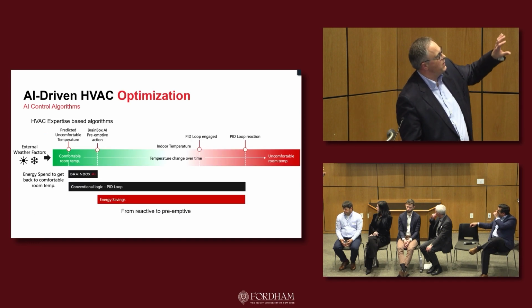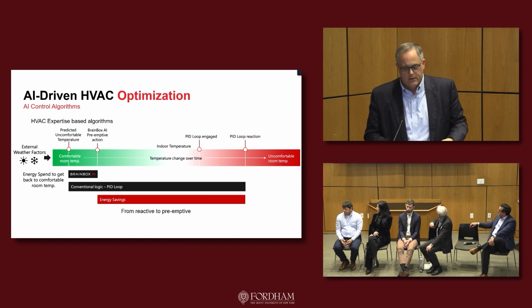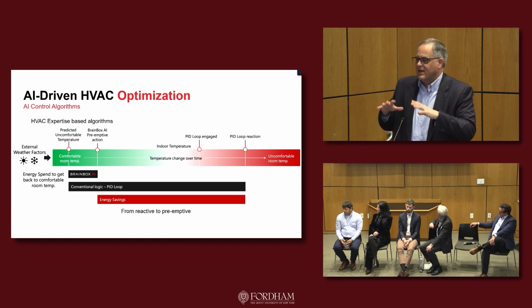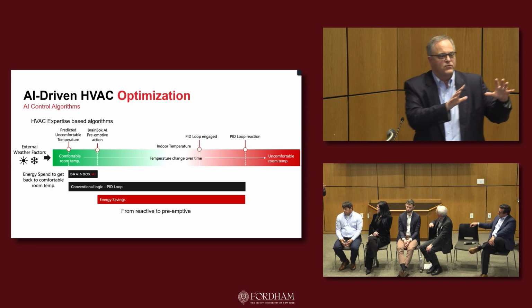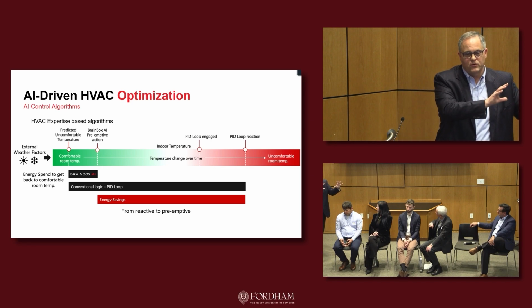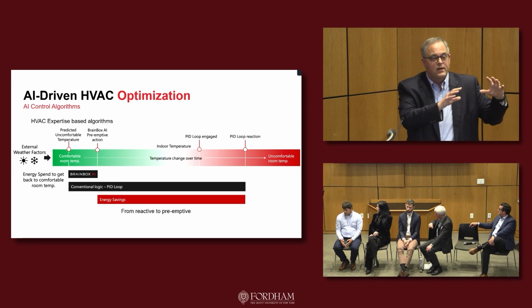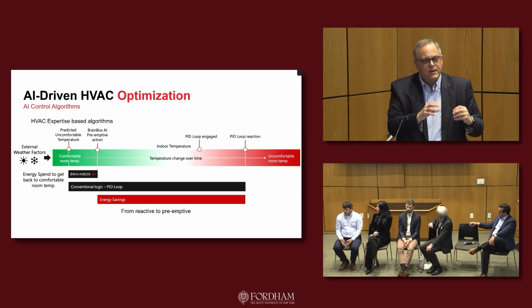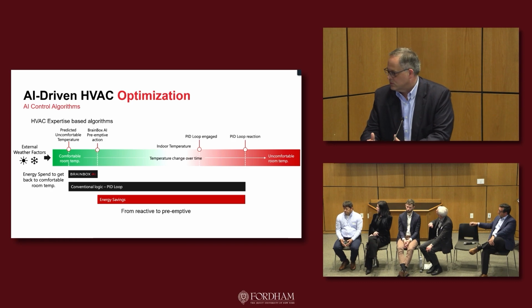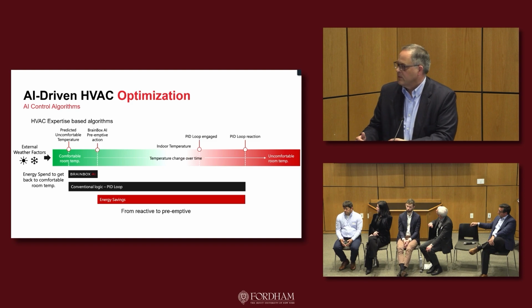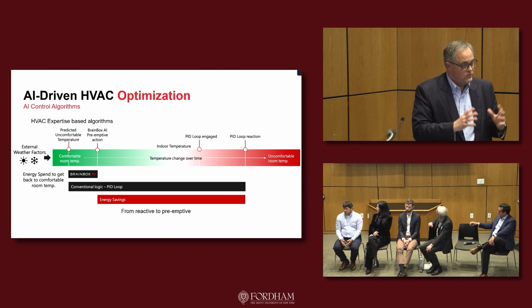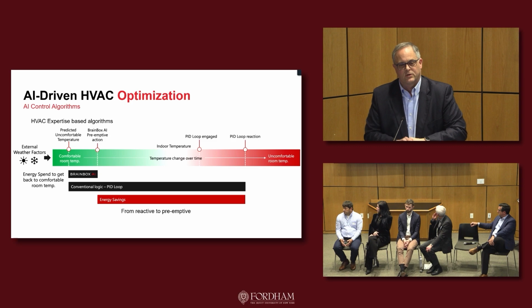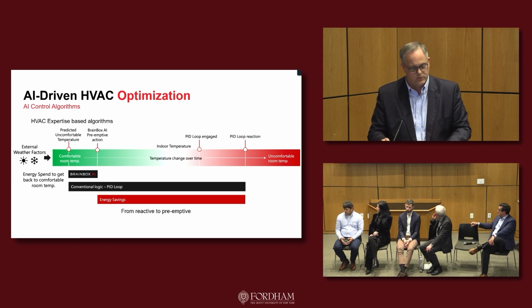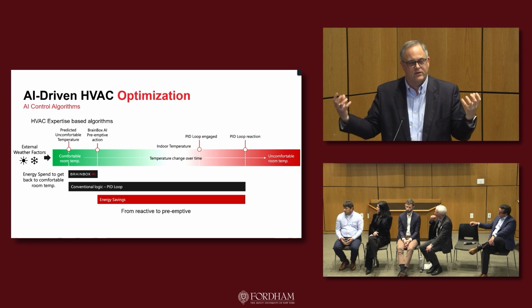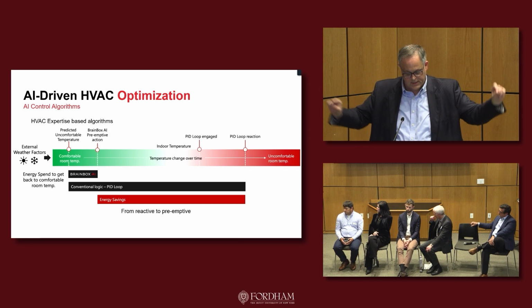We don't suspend the existing control loop; it's still in place as a safety. The preemptive control loop acts hours before, or sometimes 15 minutes before, trying to make sure the existing control sequence doesn't trigger. If it fails somehow, don't worry, because the existing control sequence is always there, doing its thing. So you have these two control loops working at different timescales.